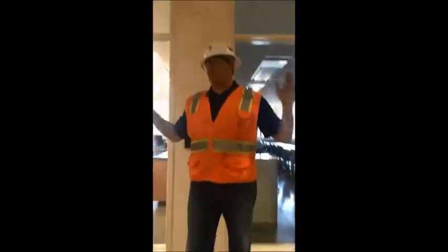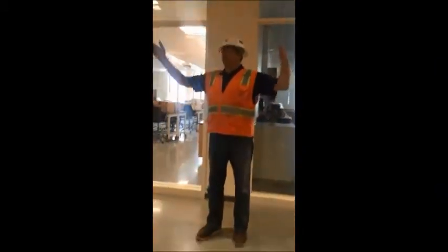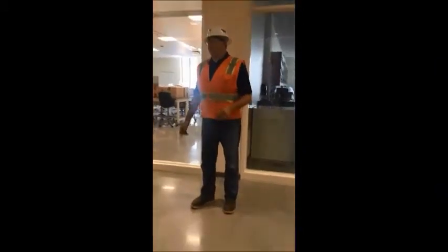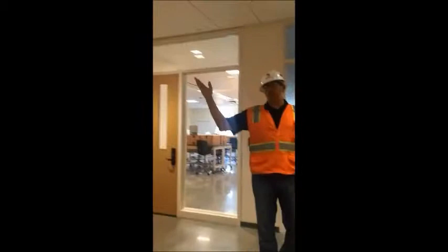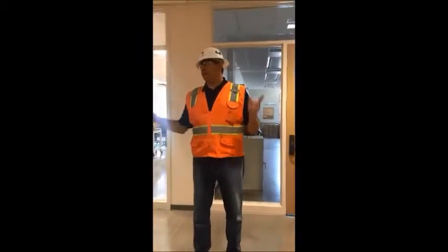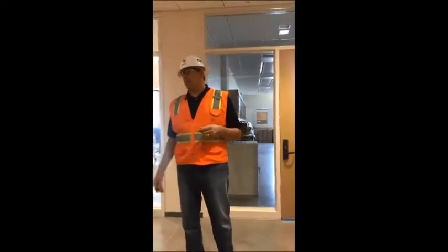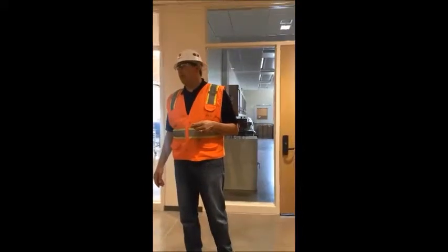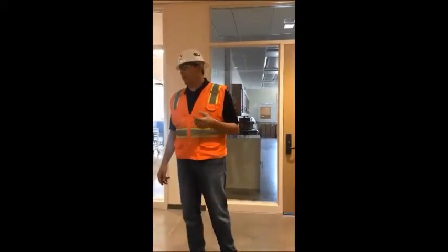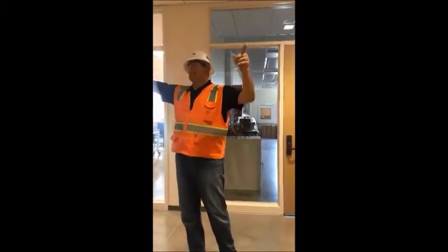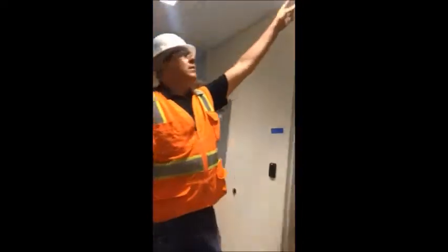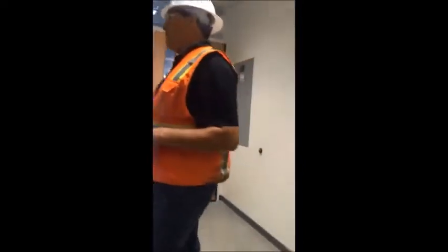Thank you. In here for domestic water, there's obviously control valves and Phoenix valves above here, and there is some on domestic water return. That's part of the domestic plumbing training, but there's actually balancing valves in the ceiling space to set. There's basically Bell and Gossett circuit setters on all the returns coming back to set. So they're basically in these corners. But this is primarily where you're going to see the balancing valves. There are isolation valves, there's Phoenix valves in these areas for the classrooms.